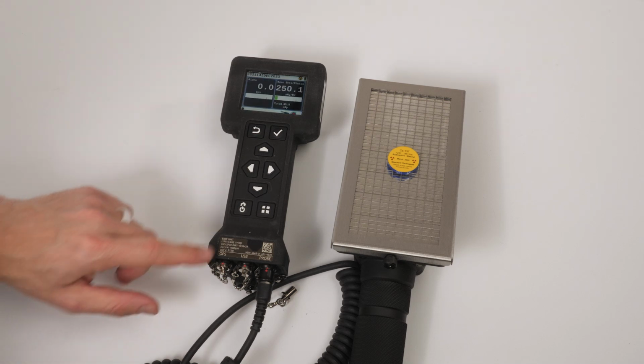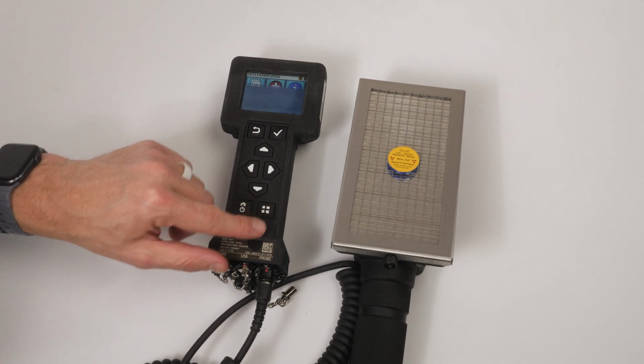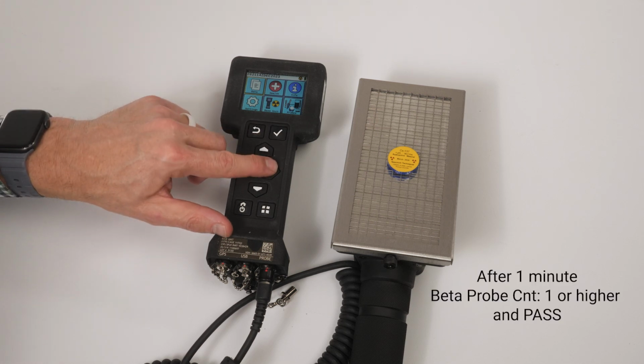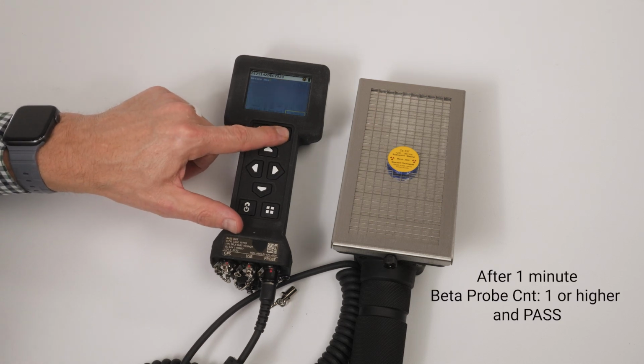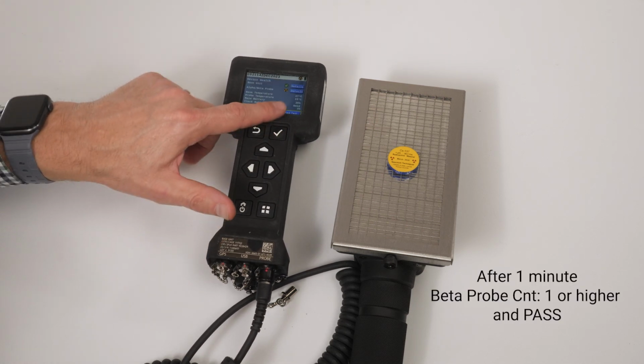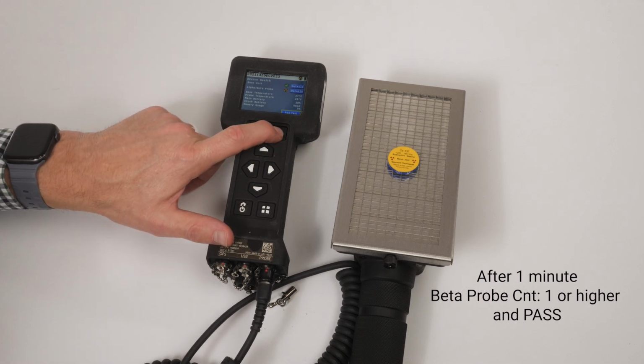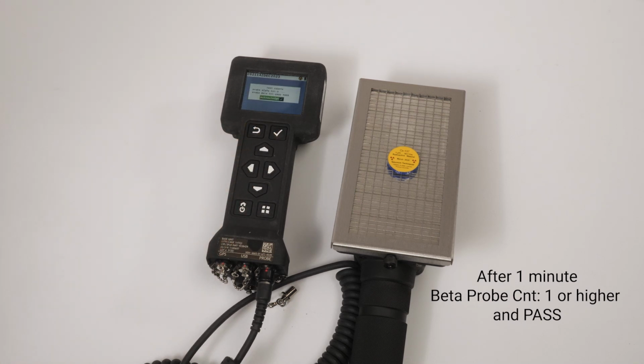To continue with the beta source check, press the menu key on the base unit, highlight the health icon, and press Enter. Highlight the Rad Test button using the arrow keys and press Enter. Leave the alpha-beta probe in direct contact with the check source for 1 minute. Verify that the probe beta count value displays at least 1 count or higher and displays pass. At the end of the minute, press the Enter key to acknowledge the results of the test.